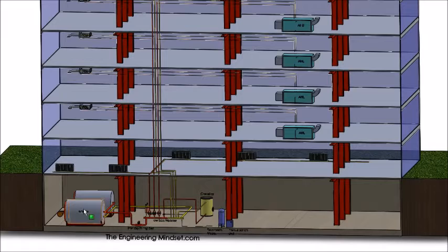Now as you can see, we've got two large boilers over here, and they are piped in parallel. And what that means is that both boilers can operate at the same time or individually. So one could be isolated and cut off and opened up for maintenance, while the other boiler here continues to run and provide heating to the building. And this is the most common type of configuration for modern heating systems. The other version would be series, and for this type of building that's not really practical.